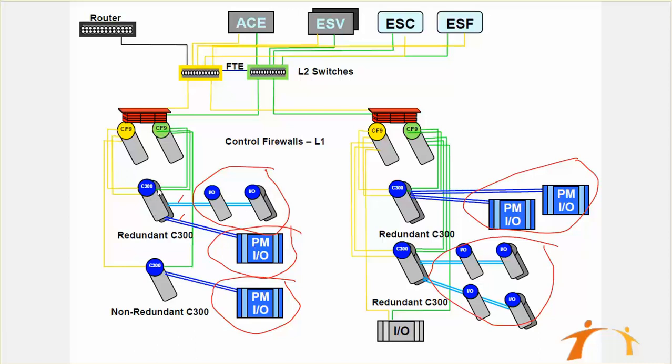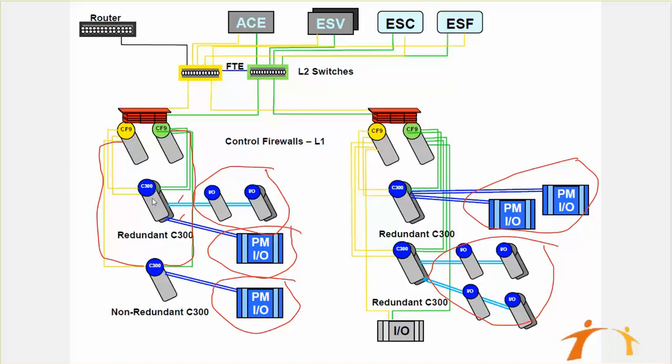Then we have our network port connected to our control firewall. The primary and secondary both come to the primary and secondary control firewall, and it is mandatory that each and every C300 controller must be connected to our control firewall module.